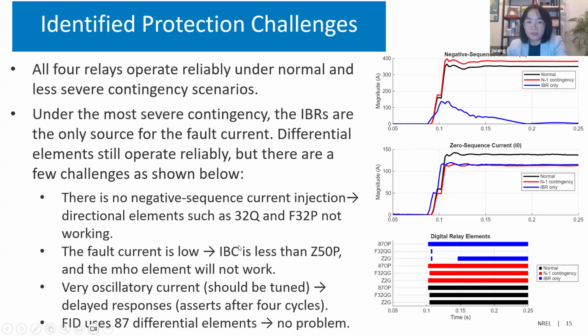So in summary, the problems are as follows. There's no negative sequence current injection. Directional elements are not operating correctly. Additionally, the mho element couldn't operate normally as well because of the low fault current. And the fault current is also oscillatory, which delays some relay elements in making the decision. The FID, fault identification logic, works reliably because we use the differential elements rather than the local elements. So this is a summary of the protection challenges.